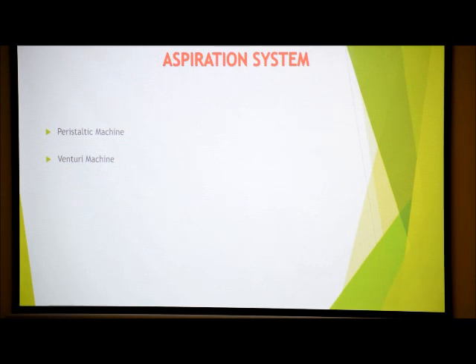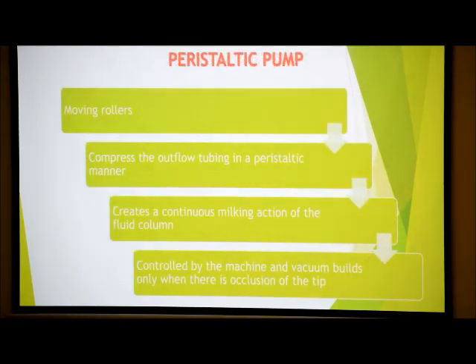So for the aspiration system, there are usually two types: peristaltic and venturi. Peristaltic is a machine where a plunger runs over the tube system, so intermittently it pushes on the tube. So there is intermittent building of pressure in the tube, which draws the fluid out of the eye.